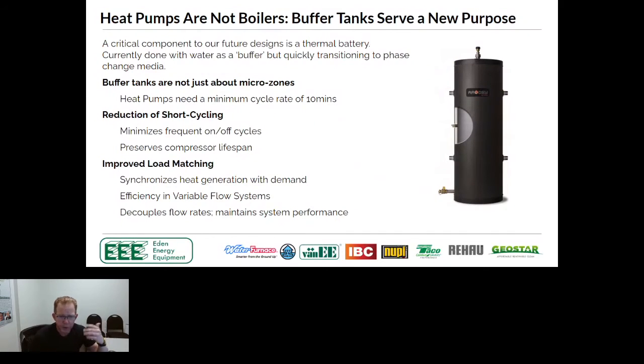The other thing that we talked about earlier is buffer tanks. So quite a few heat pumps do prefer to be put on a buffer tank. The idea of a buffer tank on a boiler is we're used to it for microzones. It's not any different from the standpoint of a heat pump. The difference is if you have a compressor that starts up and runs for 1 minute and shuts off, you're going to have all kinds of compounding issues on that compressor and the refrigeration circuit that can give you grief down the road. So a buffer tank for a heat pump serves basically the same purpose. We want to make sure we minimize the on-off times.